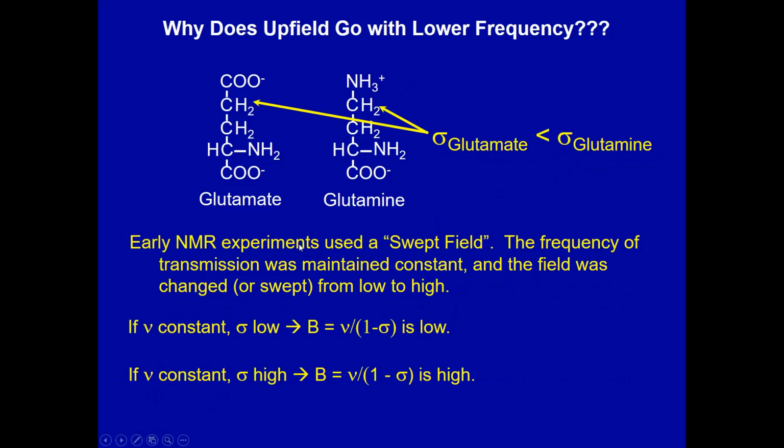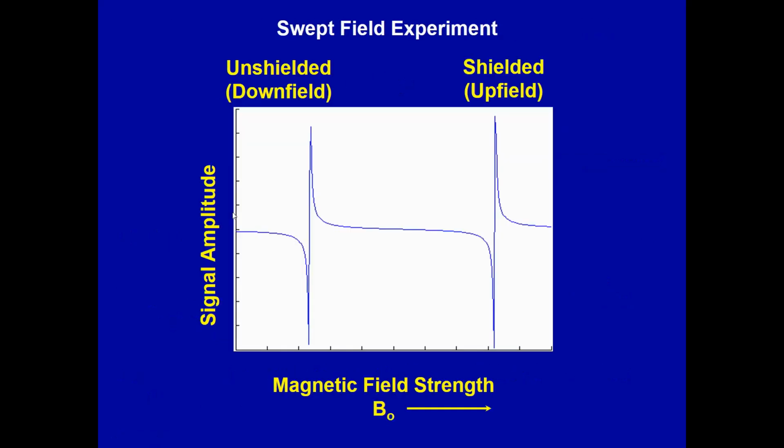Now we'll go for here to look at the original NMR studies, which were done with swept field. Currently, we transmit at the Larmor frequency. We transmit at, say, at 3 Tesla, 120 some megahertz. And it's not just one discrete frequency. We hit the sample with a band of frequencies centered around the nominal Larmor frequency. So it may be where we hit the sample with, say, 127 megahertz plus or minus 10 kilohertz.